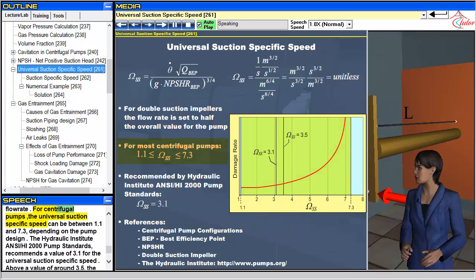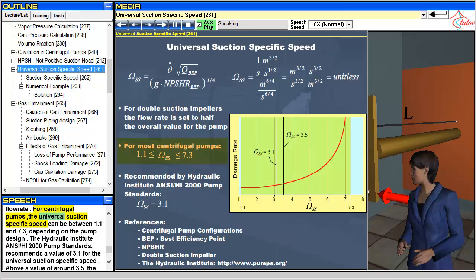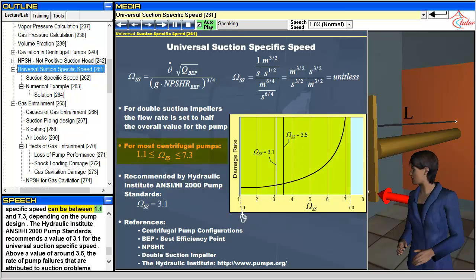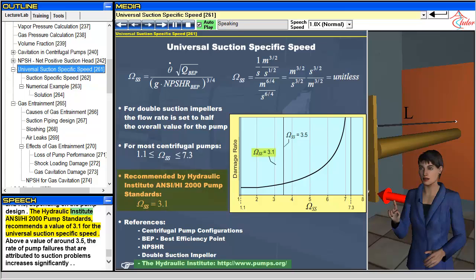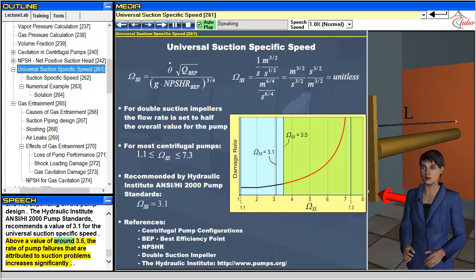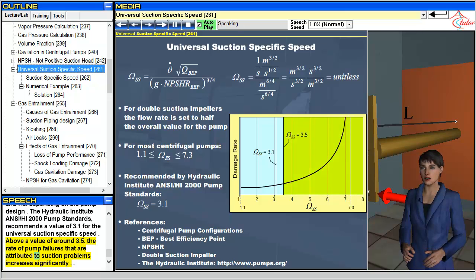For centrifugal pumps, the universal suction-specific speed can be between 1.1 and 7.3, depending on the pump design. The Hydraulic Institute ANSI/HI-2000 pump standards recommends a value of 3.1 for the universal suction-specific speed. Above a value of around 3.5, the rate of pump failures that are attributed to suction problems increases significantly.